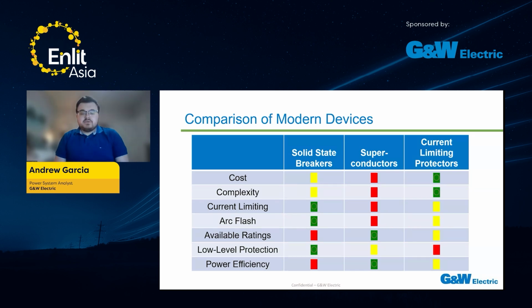Now, if you want the best deal for current limiting, solid state breakers are definitely the best case. Once again, they completely clear that fault in microseconds, which virtually eliminates any exposure to fault energy. Second place comes in current limiting protectors. They're a very nice current limiting device that limits faults to a significantly lower level. Last is superconductors, just because if you don't have them run for miles or kilometers, they're not going to be able to limit that much fault current. And that same pattern applies once again for arc flash, because it's inherently limited to current limiting capabilities. So solid state breakers come in first, current limiting protectors come in second, and superconductors come in last.